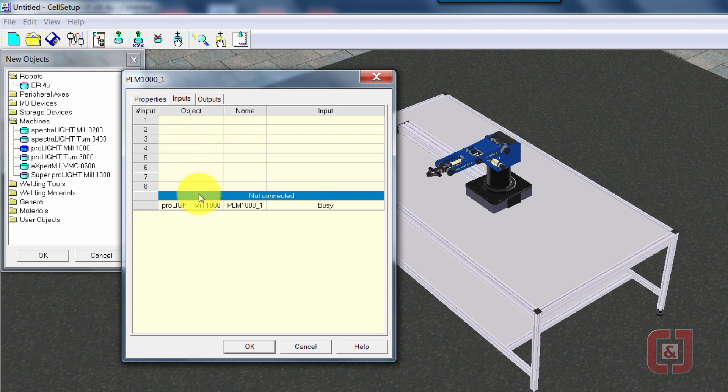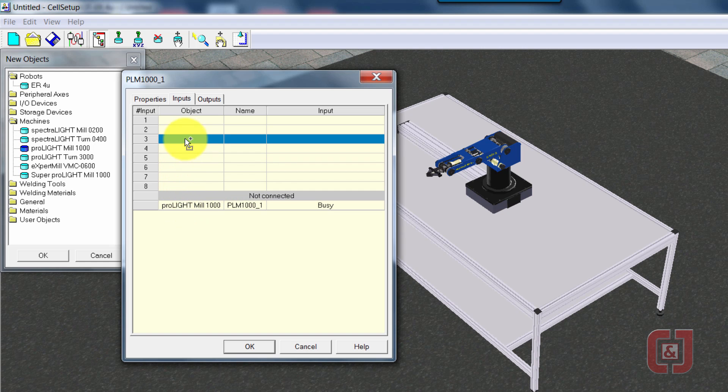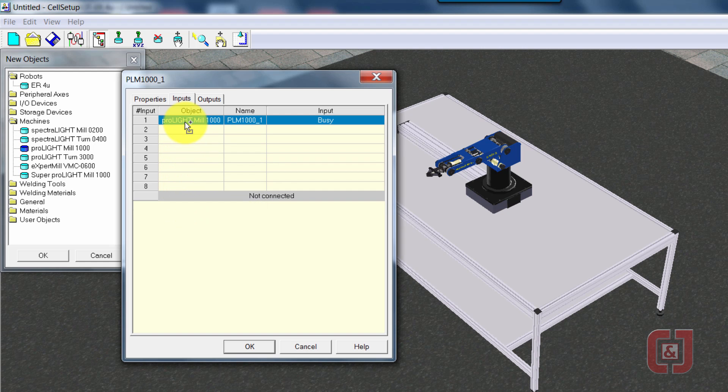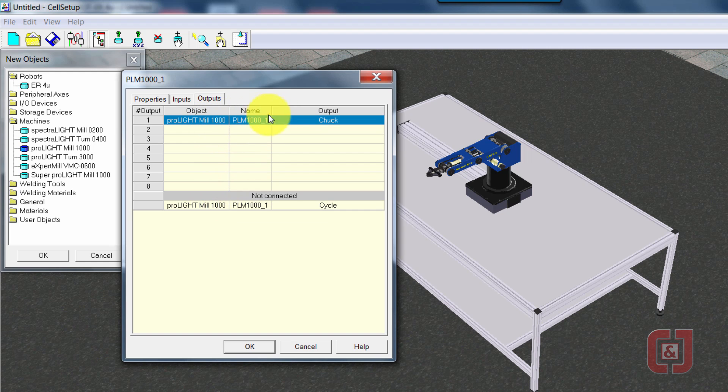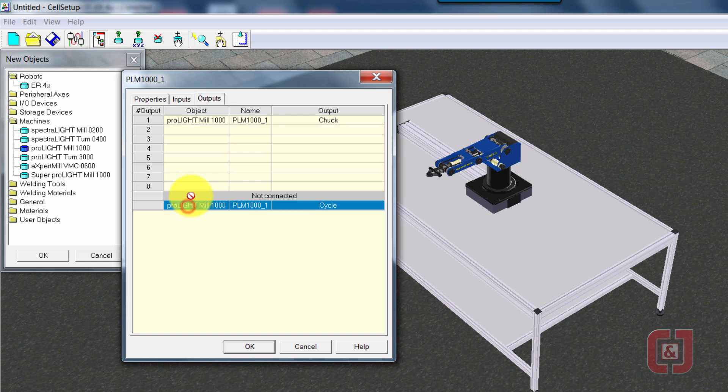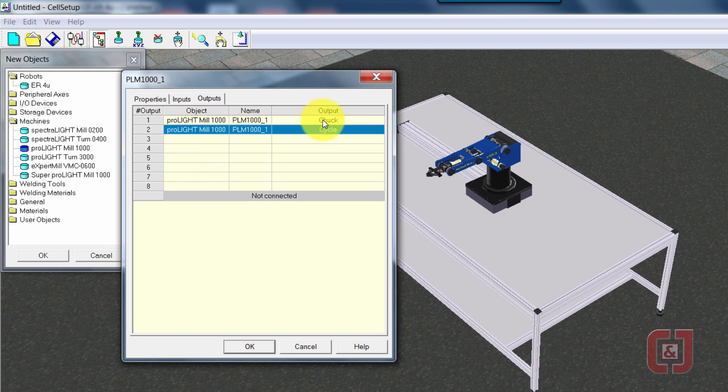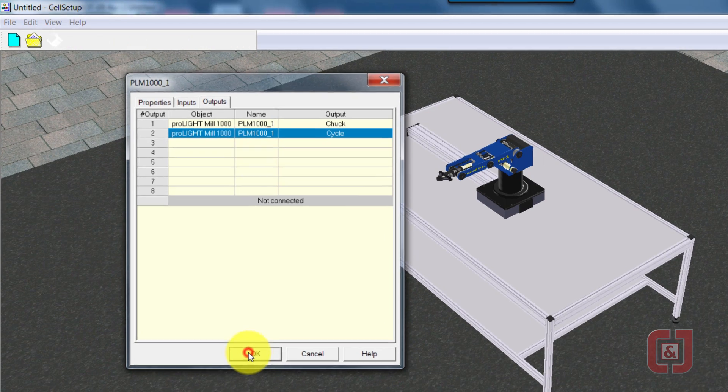Inputs. This input is the mill telling the robot that it's busy. So it's still running a process, and it gets to do that on input one. Outputs. The first one, the chuck, is what we call the vise. The vise is what we're actually going to hold the block in with. So this is the robot telling the mill to close the vise. This is the robot telling the mill to start a cycle. Select OK.